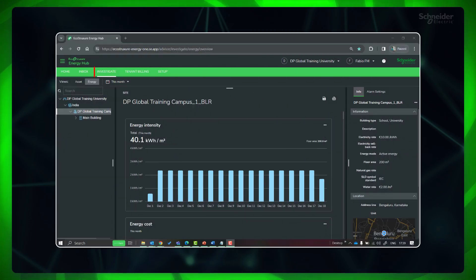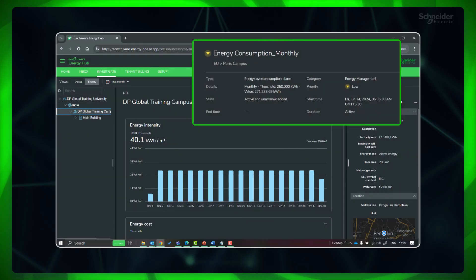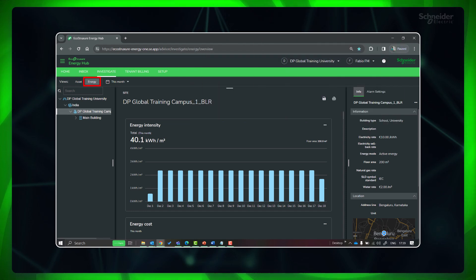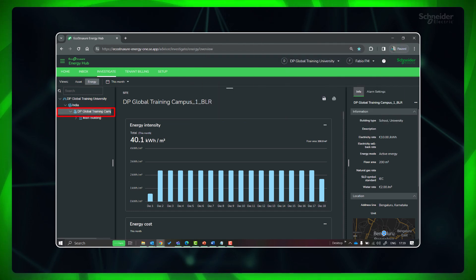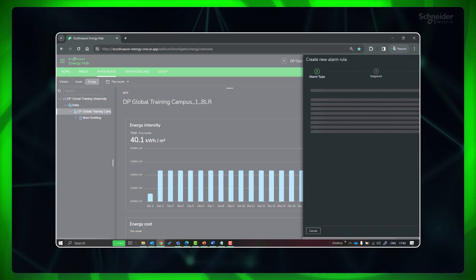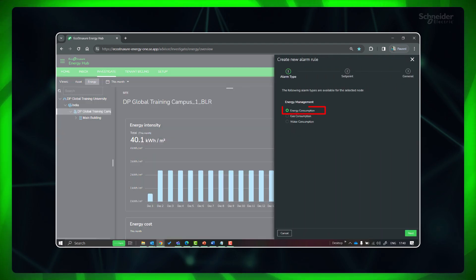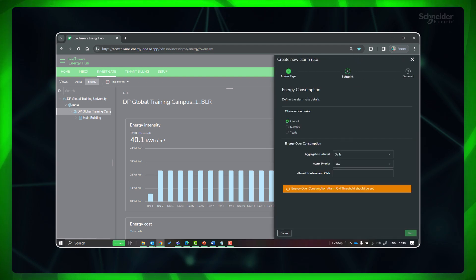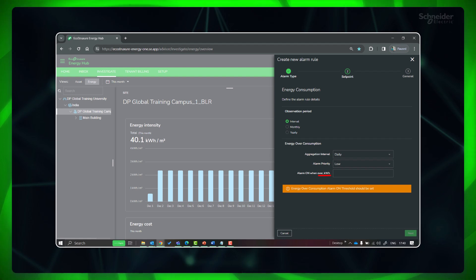For setting an energy consumption alarm at site level, go to Investigate. In the Navigation panel, click on the site. In the Information panel, click Alarm Settings, then Add Alarm Rule, and select Energy Consumption. Click Next. Please note the alarm settings are based on active energy, irrespective of the energy mode you had selected earlier.